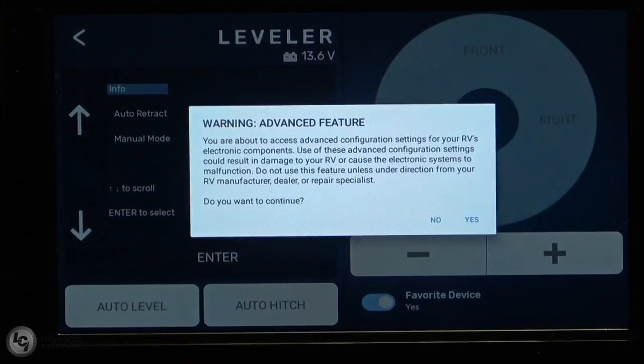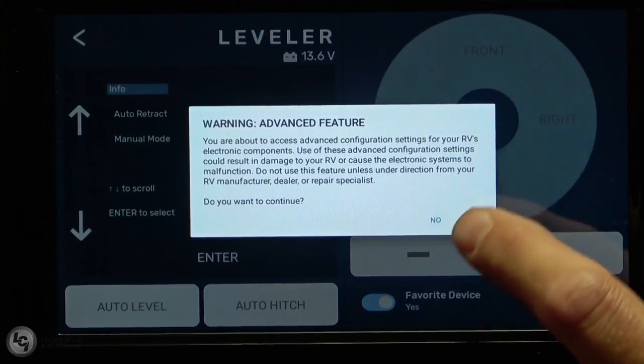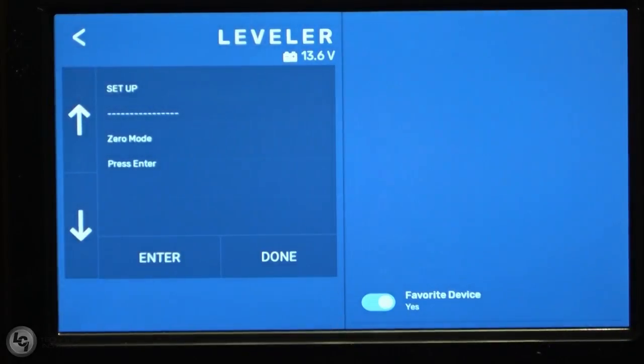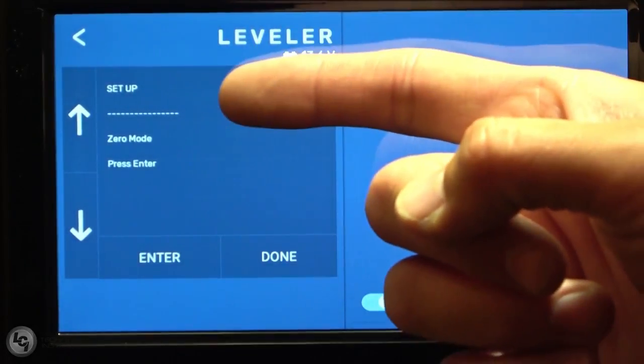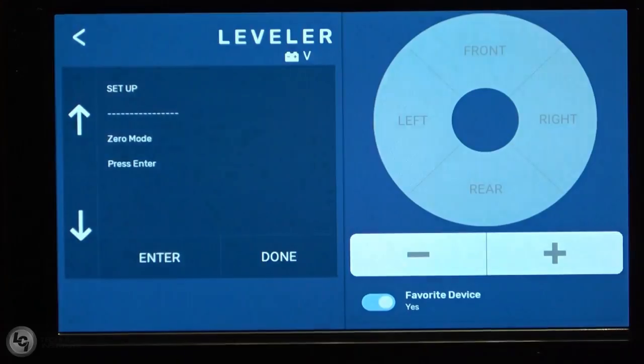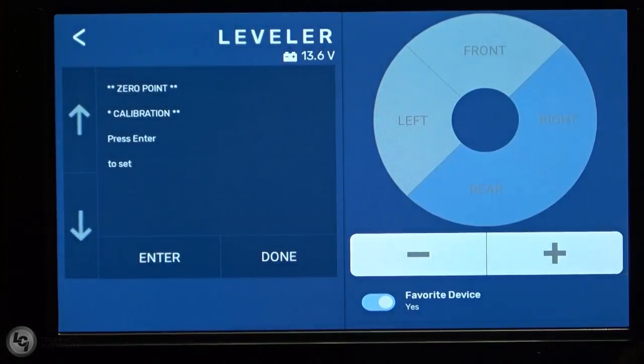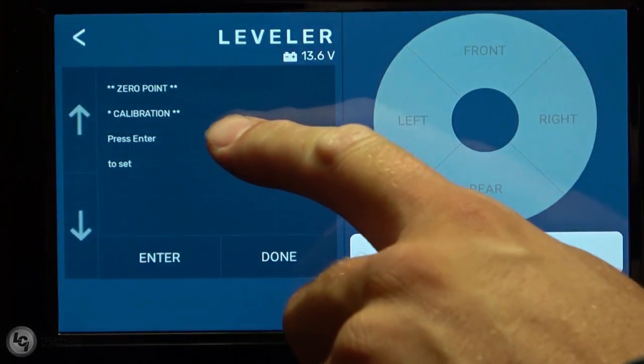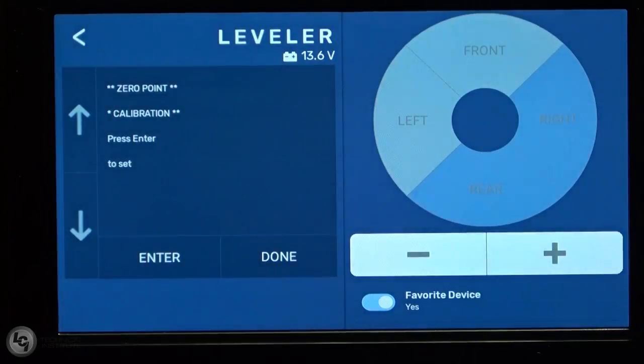It says you're entering advanced features. If you're trying to set your zero point here, you're going to want to hit yes. If you've inadvertently hit the leveler name at the top there 6 times, go ahead and hit no. After you hit yes, it'll say setup, zero mode, press enter, so we'll go ahead and hit enter. Now it says zero point calibration, press enter to set.